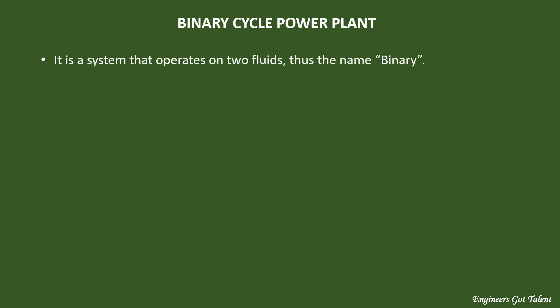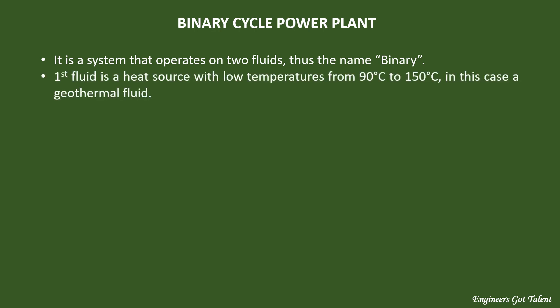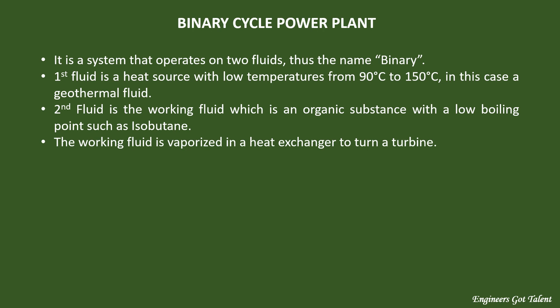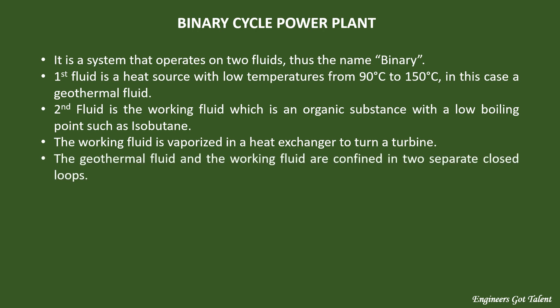The Binary Cycle Power Plant System is a system that operates on two fluids, thus the name Binary. The first fluid is a heat source with low temperatures from 90 to 150 degrees Celsius — in this case, a geothermal fluid. The second fluid is the working fluid, which is an organic substance with a low boiling point, such as isobutane. The working fluid is vaporized in a heat exchanger to turn a turbine. The geothermal fluid and the working fluid are confined in two separate closed loops.